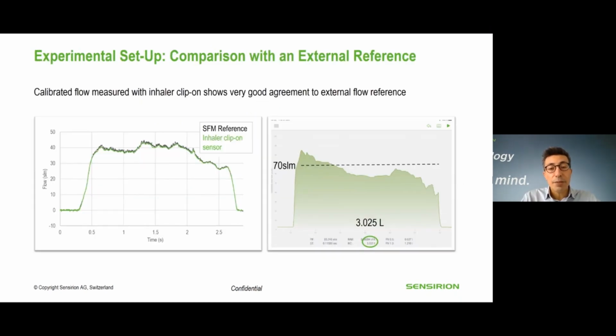Following this calibration step, we made a control experiment consisting of comparing the clip-on flow sensor signal to the reference. The curve to the left shows a very good agreement. We also compared the total measured volume to a syringe pump reference of 3 liters. The results to the right show a good agreement with 1% error.